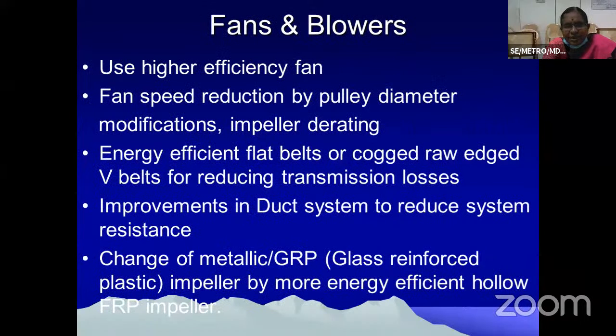Fans and blowers: use higher efficiency fans, fan speed reduction by pulley diameter modification, impeller derating, energy efficient flat belts or cogged raw edge V belts for reducing transmission losses, improvement in the duct system to reduce system resistance, and change of metallic or glass reinforced plastic impellers to more energy efficient FRP impellers.